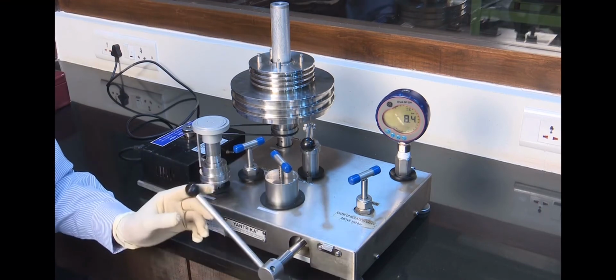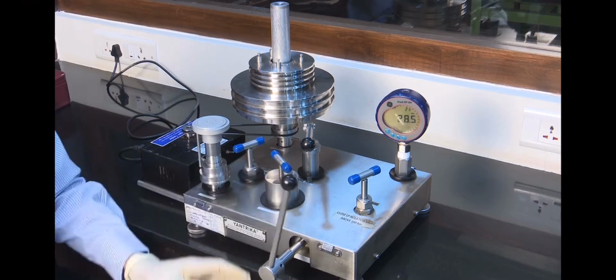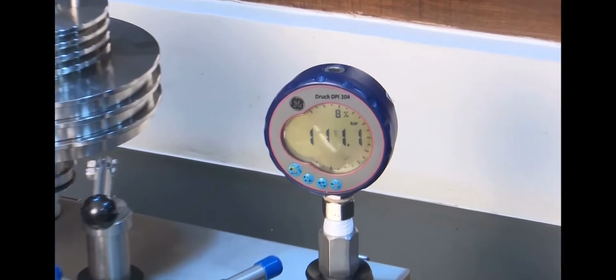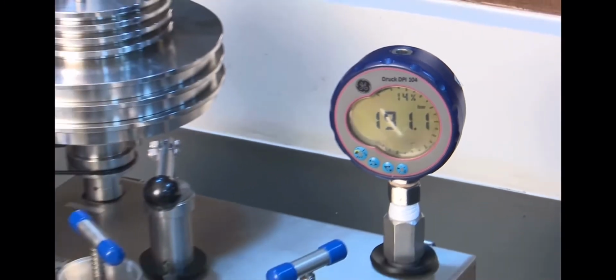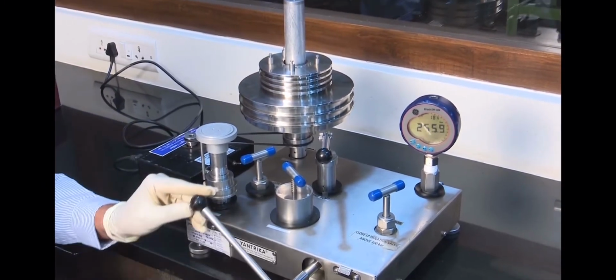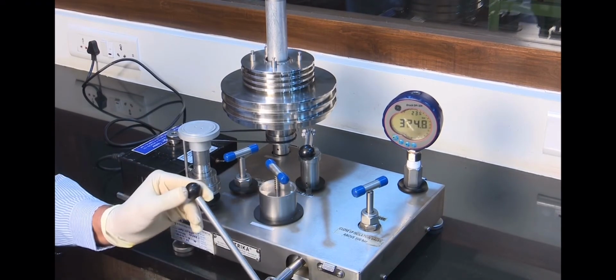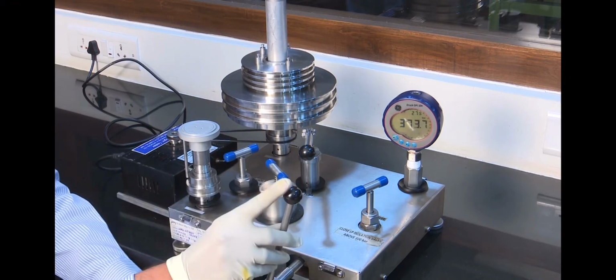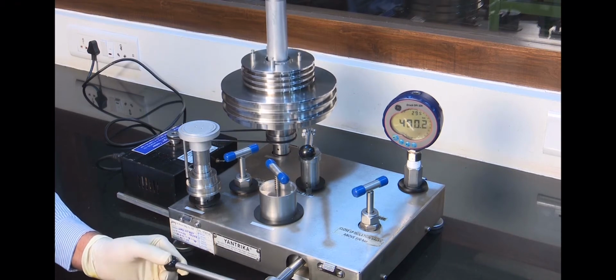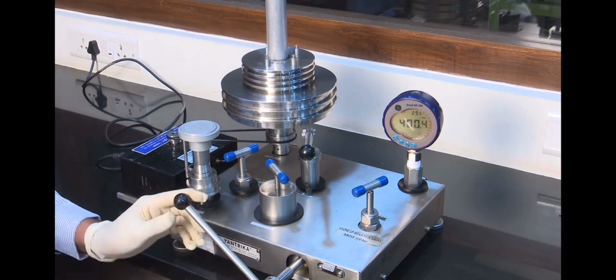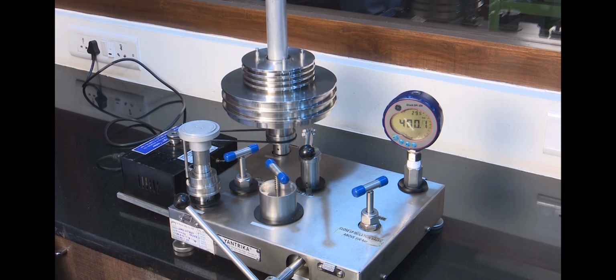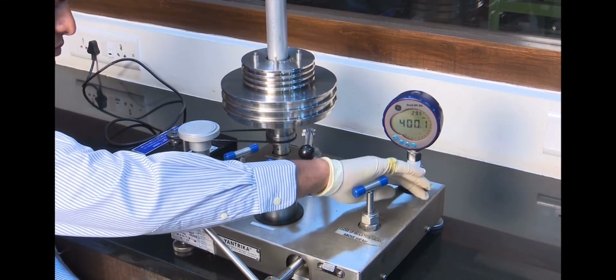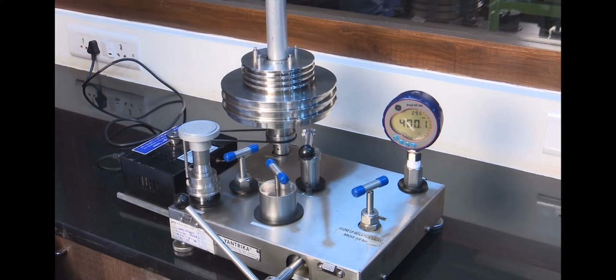Now operate the handle of the dead weight tester clockwise to raise pressure until the free piston and the weight rises up. Now operate it till full range, means maximum pressure on UUC is achieved. Perform leak test at maximum pressure on UUC. Hold it for 2 minutes at full pressure to check leaks if any. Here no leakage is found, so we will proceed for calibration.